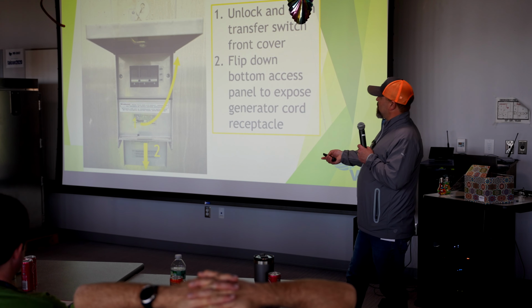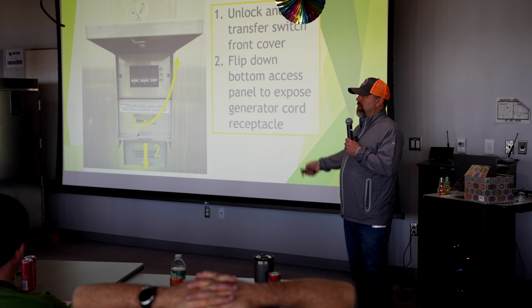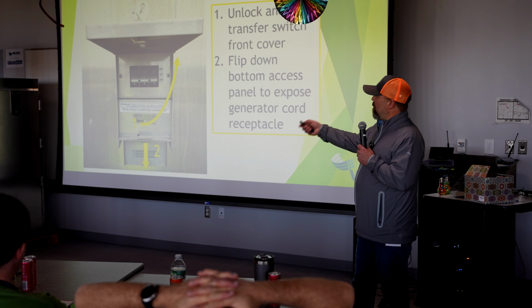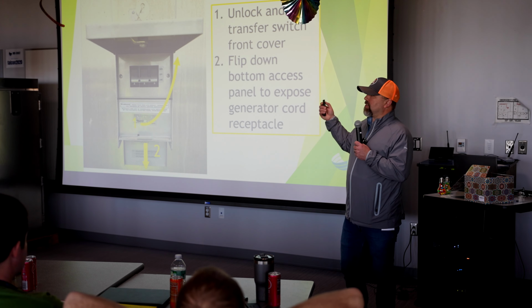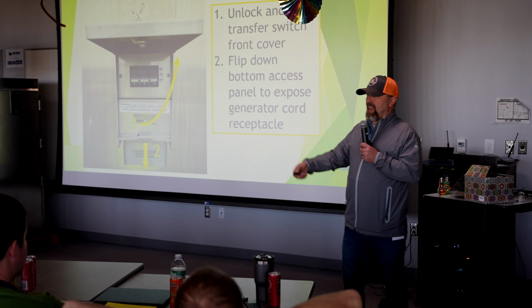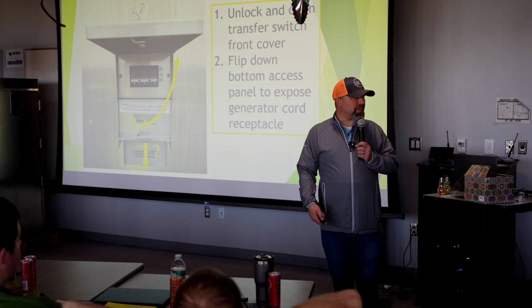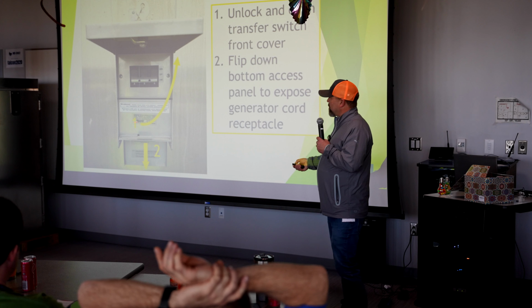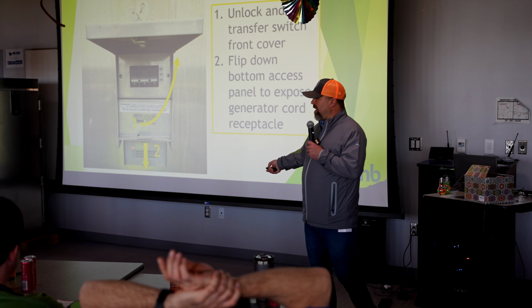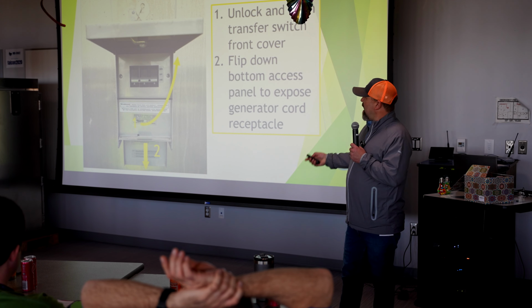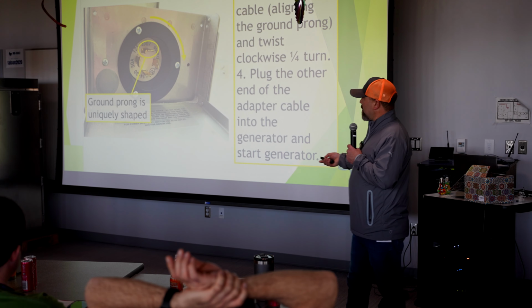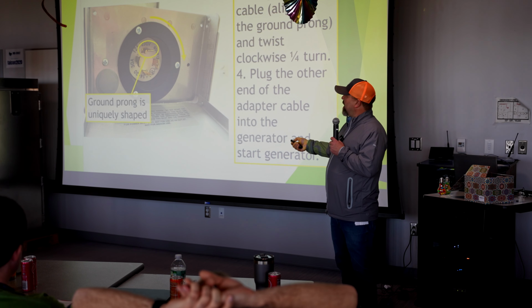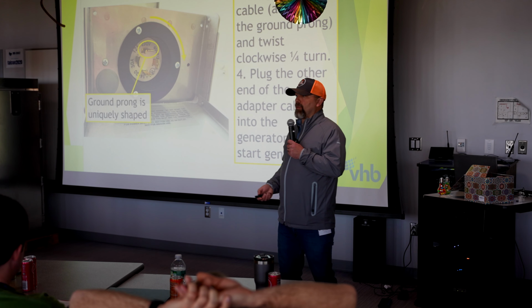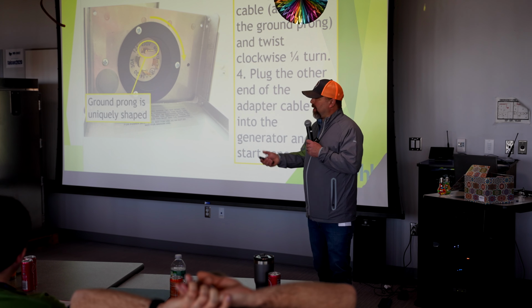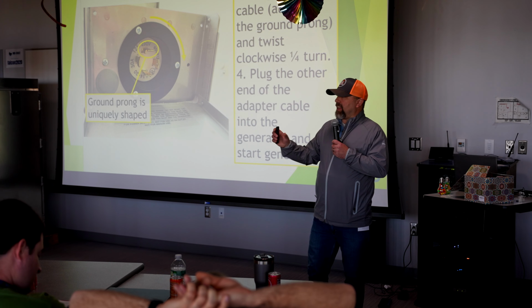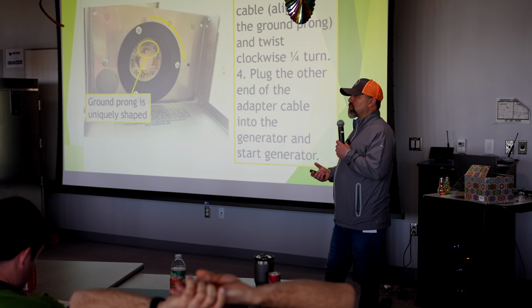So real quick, if you show up and you're looking to transfer this, the utility power is out, and you're the person coming out with a generator, hook it up. When you go in, these are locked. By and large, the keys can be stored inside the cabinet, or the town or agency handles the security on who has the keys. Once you pop open that transfer switch, you pop the front cover open, and then underneath, it can be a little deceiving. There's an access cover that you have to flip down, and that will expose the generator plug, the twist lock plug. When you connect it up, bear in mind you're going to have one terminal that looks different. That's your ground terminal. It's keyed specifically, so you can't plug it in incorrectly. But it's really important that when you plug that in, you give it a quarter turn twist so that you lock it into place.